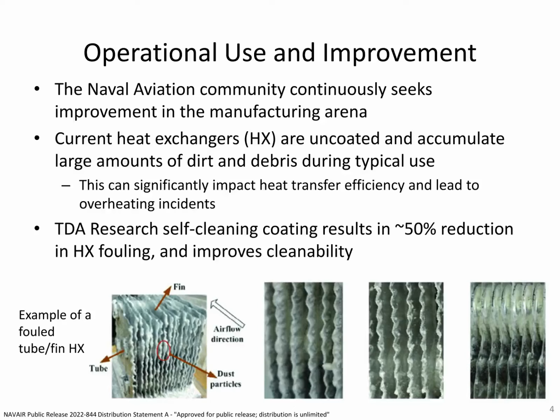In this project, TDA Research has developed a self-cleaning coating that results in a 50% reduction of the heat exchanger fouling. You can think of this 50% reduction as a doubling of the service life of the heat exchanger before cleaning is required. Our coating also improves the cleanability of the heat exchanger, meaning that the maintenance of the heat exchanger will be easier as well.